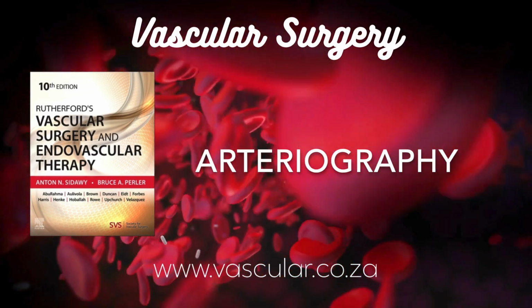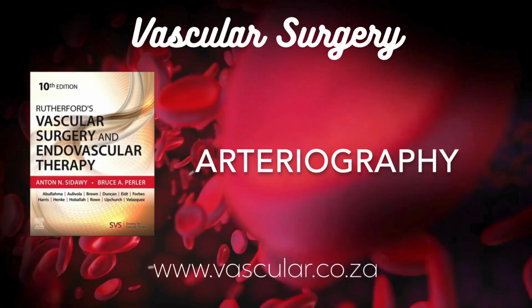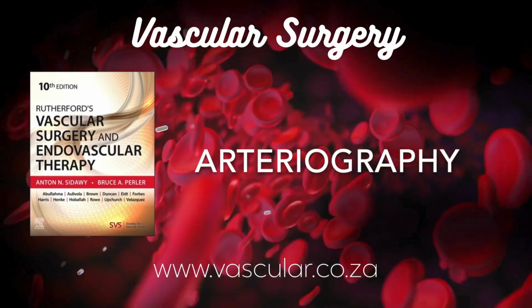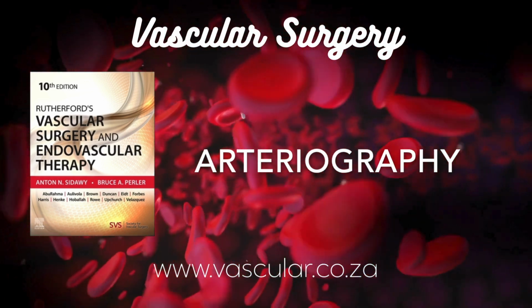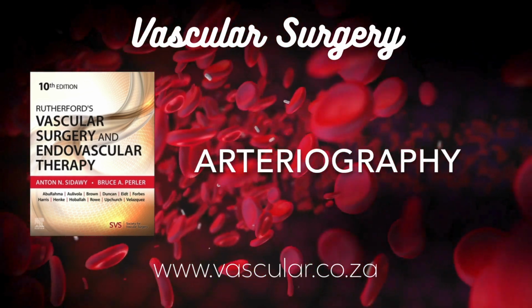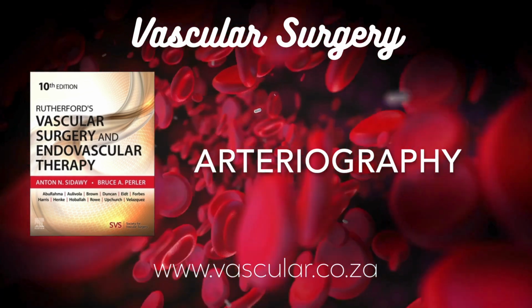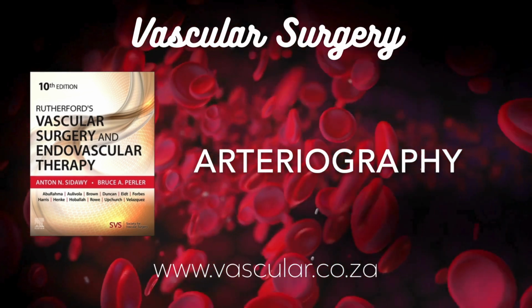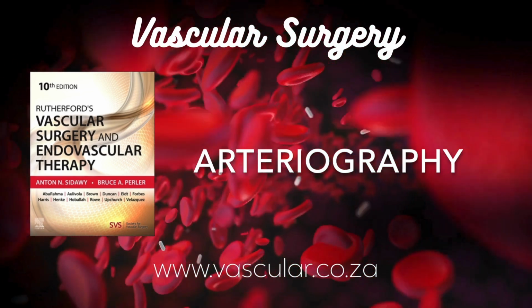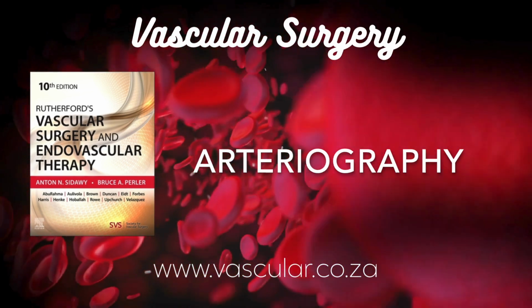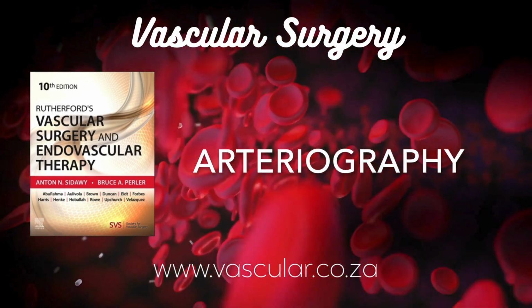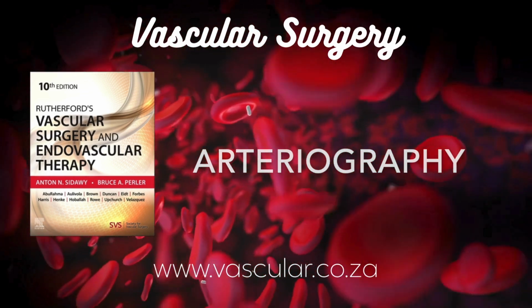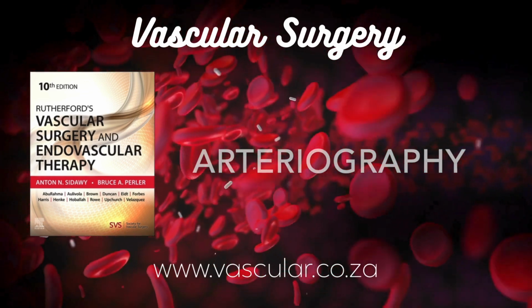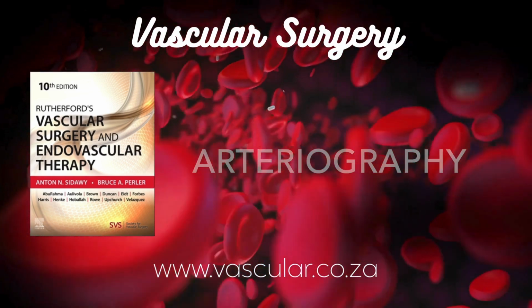And you have to adjust the settings, right? Higher pressure for big vessels like the aorta, lower pressure and slower rise for smaller ones like the superficial femoral artery to avoid damaging them. You might hear docs talk about 20 for 40. That means 20 milliliters per second for a total of 40 milliliters. Got it. Any other perks? A big one is radiation safety. The operator can stand further back from the X-ray source during the power injection, reducing their dose.